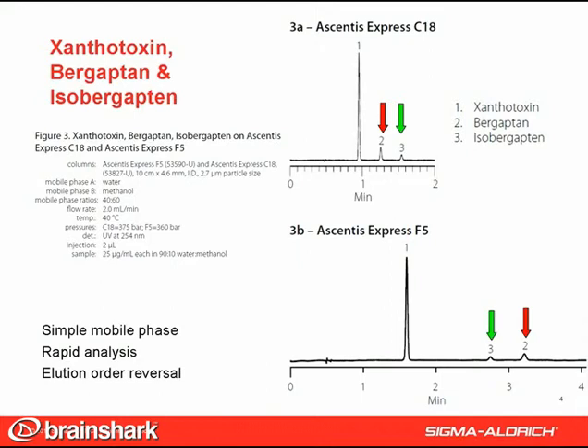Why is the ability to reverse elution order useful? Primarily for trace analysis, where you want the compounds in excess to elute after the trace level compounds. Using different phase chemistries is the most effective means to alter elution order. We have provided this ability by offering a wide variety of Ascentis Express phase chemistries, including C8, C18, phenylhexyl, F5, HILIC, and AMIDE, with others currently in development.